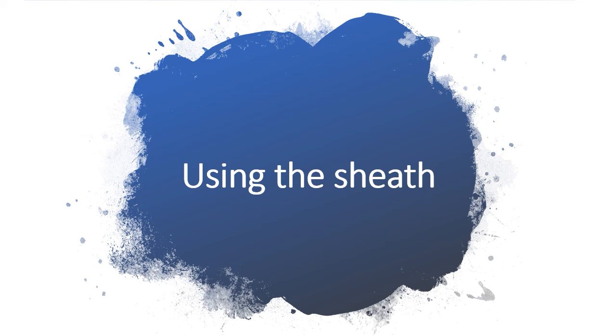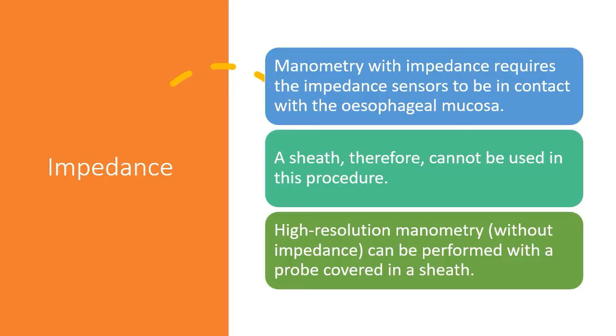High-resolution manometry catheters can be used with sheaths. Manometry with impedance requires the impedance sensors to be in contact with the esophageal mucosa. A sheath, therefore, cannot be used in this procedure. High-resolution manometry without impedance can be performed with a probe covered in a sheath.